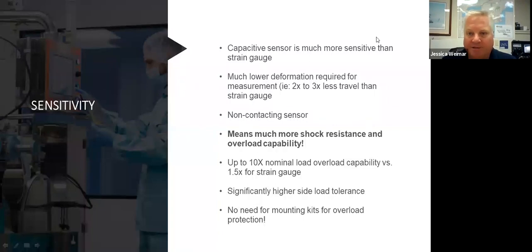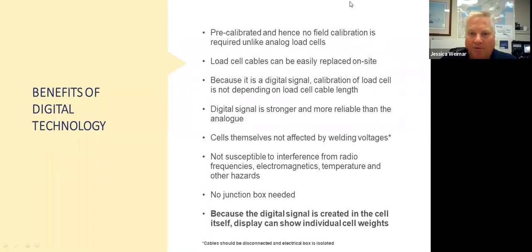I think we've finished this slide. So there's a couple other things that are really interesting about the Alfa system. I told you earlier that the smarts, or the intelligence, is in the load cell. So what does that mean? The cell itself can actually be pre-calibrated at the factory and come with a factory certification on it. You can't do that with the strain gauge load cell. There's no way, because there's no intelligence in the cell itself. It's a redundant opportunity to be sure that the system has met third-party calibration.